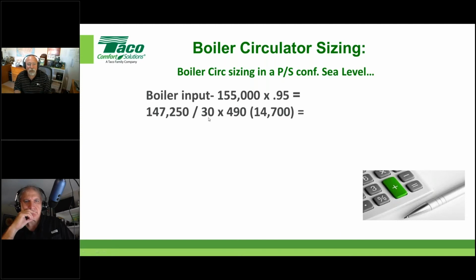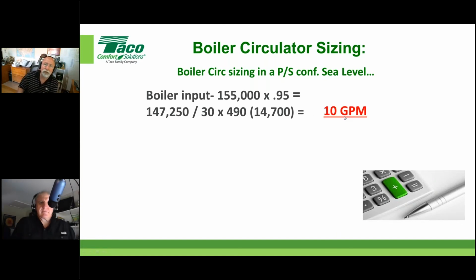If I'm going to run at a 30-degree delta T, remember, I'm going to use whatever number the manufacturer will give me, but if I don't know, and it's a condensing boiler, 30 is pretty safe. You saw that on everybody's information for the most part. You can use 500 if you want to. Hot water is actually 490. 140-degree water. So I just do this math and it says I need 10 gallons a minute. That's what we're going to use for our exercise, a 10 GPM pump.